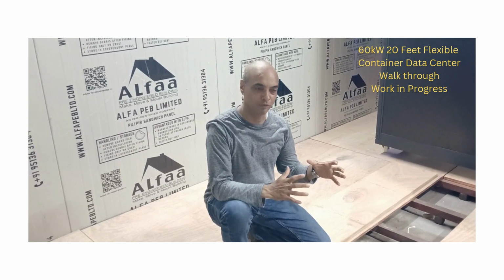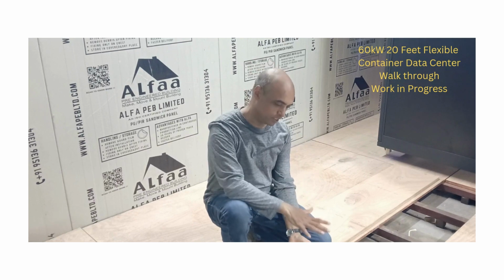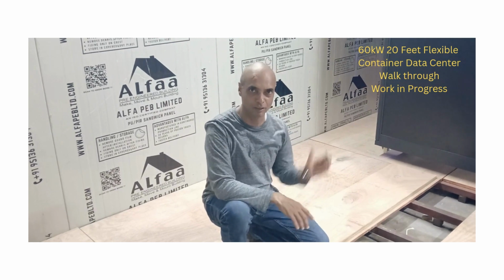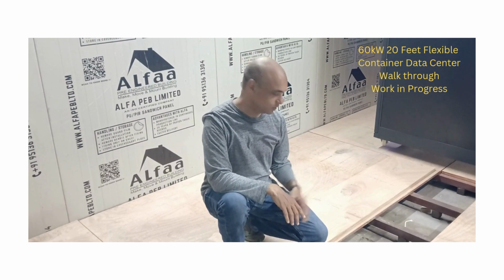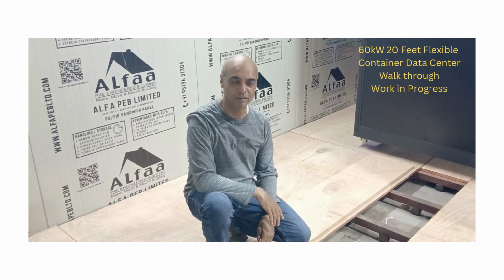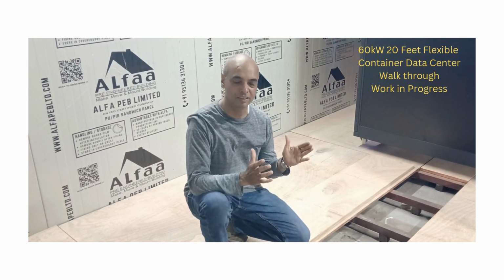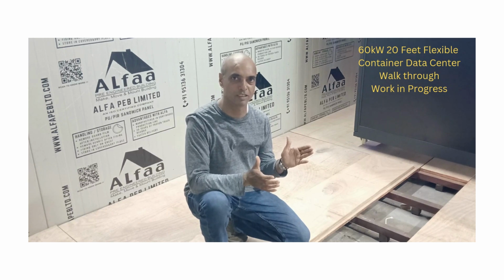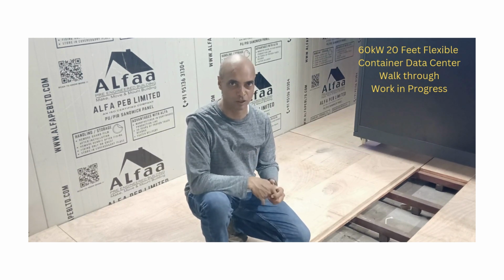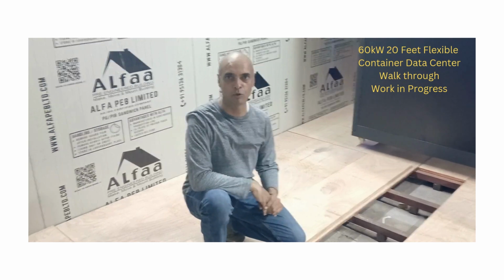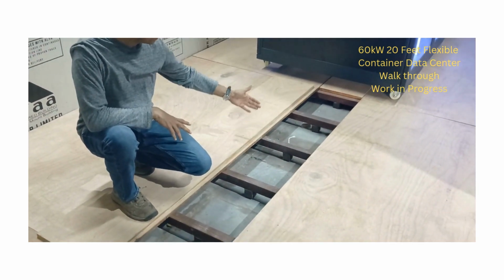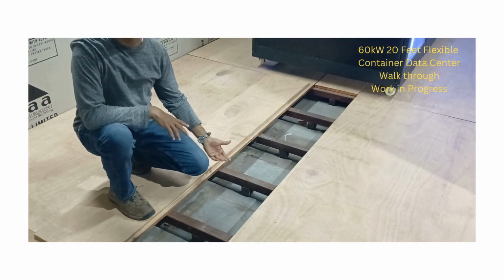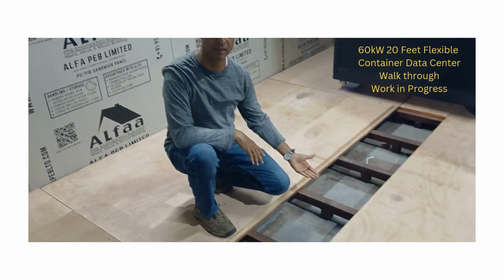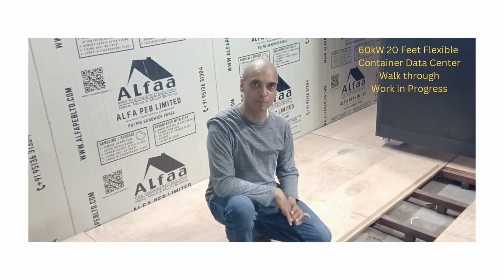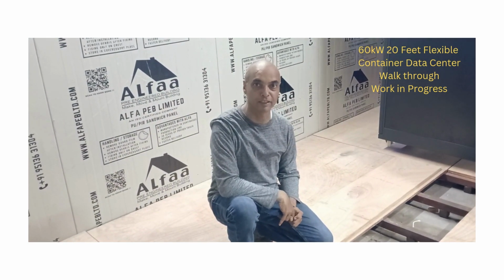We also have an option to put a 1 foot high container floor for installing racks on top. This is important because the steel rack can hold anywhere between 1500 to 2000 kgs of weight including servers. That's why we've focused on the flooring: a wooden floor on top, and below it a steel frame which is also ISO steel certified. That's one of the important features for container-based data centers.